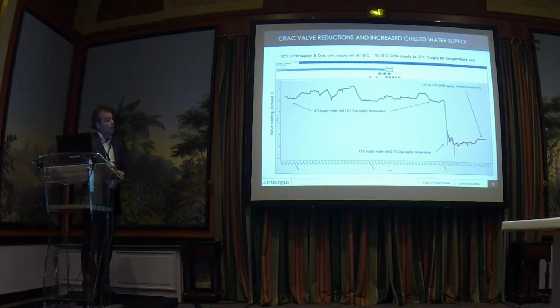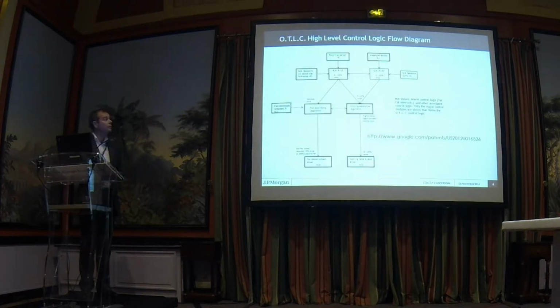And then along here we're still running 12 degrees. And then I put the supply water up with the CRAC units from 12 up to 15 degrees. And I think we jumped about 15% across all the CRAC units on average. And notice how that line there is nice and flat and straight. I was saying about here that the temperature of the water could vary now a good few degrees, but that will still stay the same. Well, it will go up a bit, but the temperature out of the CRAC unit will always remain the same.